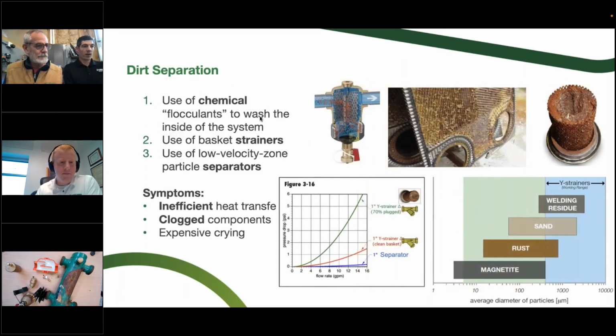Yeah. Okay, so for dirt separation, there will be non-ferrous dirt in a system, even a brand new system. Sometimes we get those questions: hey, it's radiant, it's a stainless steel heat exchanger. The only thing that's ferrous in this entire brand new system is the expansion tank and the volute of the circulator. Do I really need high performance dirt separation? You could catch some of that stuff with any basket strainer or any dirt separator.